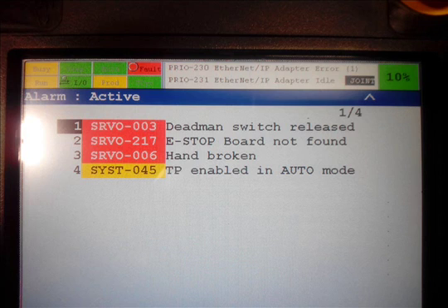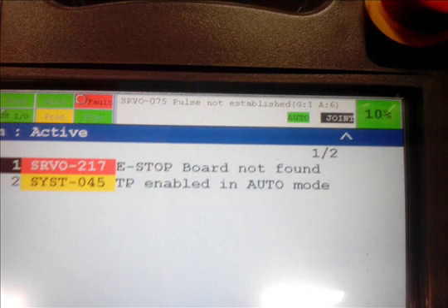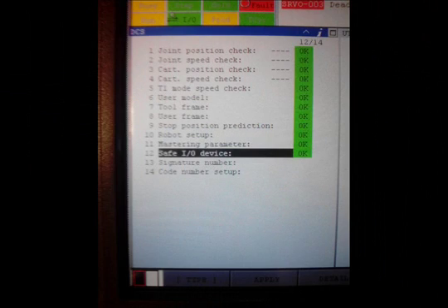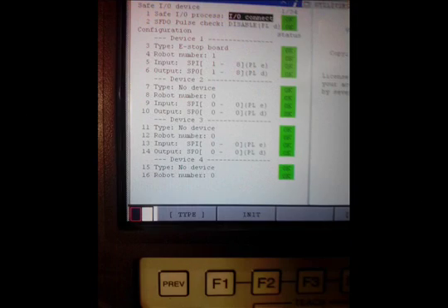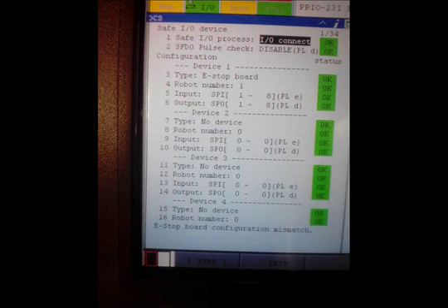So the robot can be jogged, programs can be written and all that. E-stop, a fuse on the E-stop board was blown. So I have to replace that. Checking the dual check safety settings.